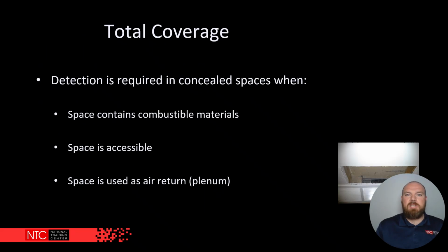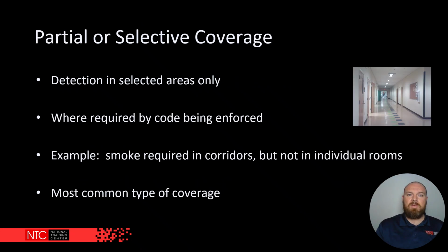Detection is required in concealed spaces when the space contains any combustible materials, the space is accessible to the general public in the building, or if the space is used for an air return or plenum airspace. Gonna need total coverage for that.